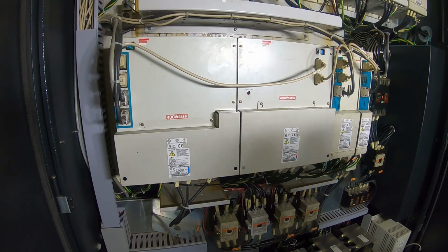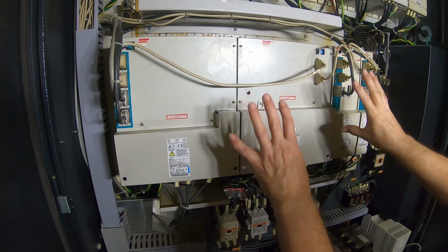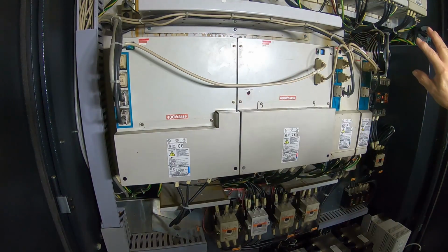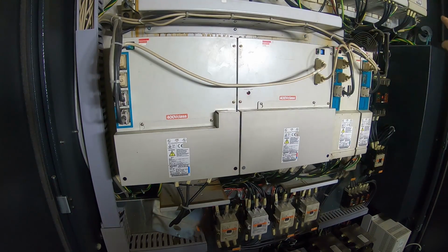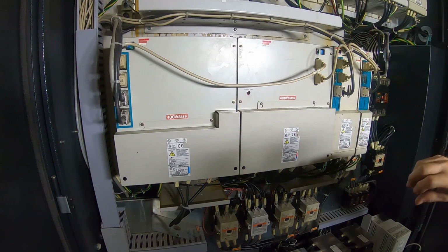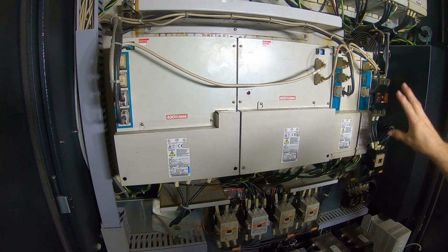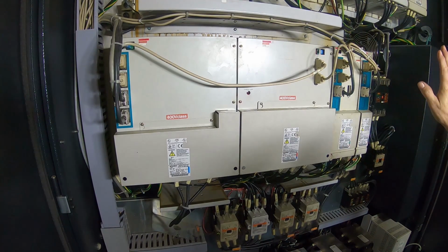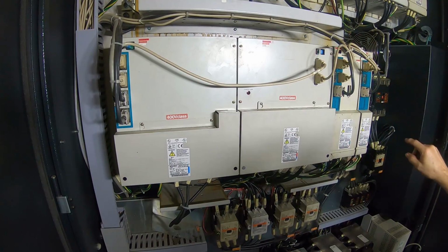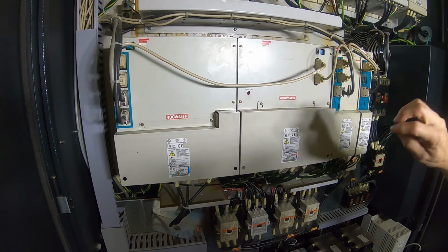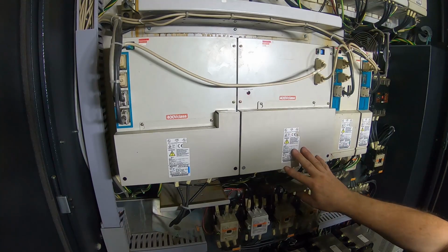What I didn't understand about this machine is if you leave the main circuit breaker, or the incoming circuit breaker power, on, it leaves all of this powered up. The only thing it's not actually powering is the servo drives. When you release emergency stop, it enables those. But even with the emergency stop depressed and the main switch on but the control off, all of this still has power to it.